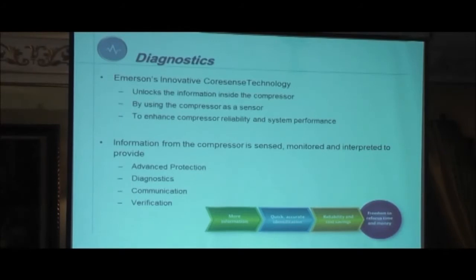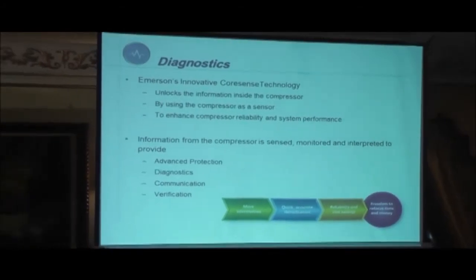Now that we've covered the mechanical side, the most important aspect about these new compressors is the electronics and what we call diagnostics. What we're trying to do is install electronics so that we use the compressor as a sensor. By fitting sensors into the compressor, we can extract operational information from that compressor. And by doing that, we can increase the reliability and improve the safety features of the compressor.